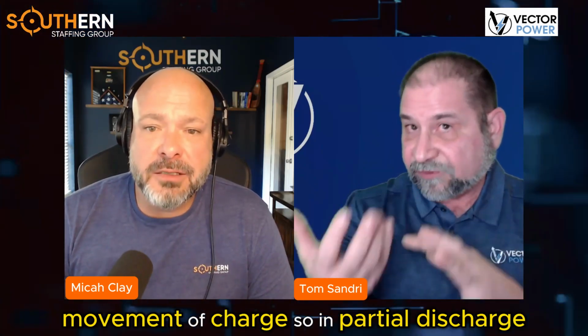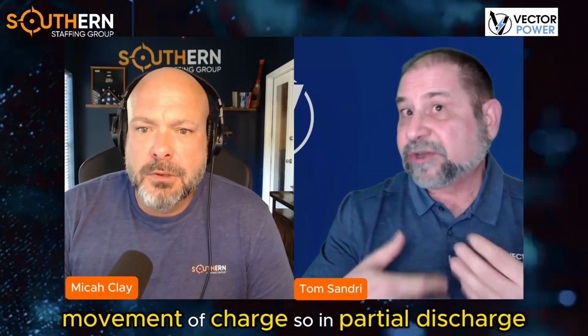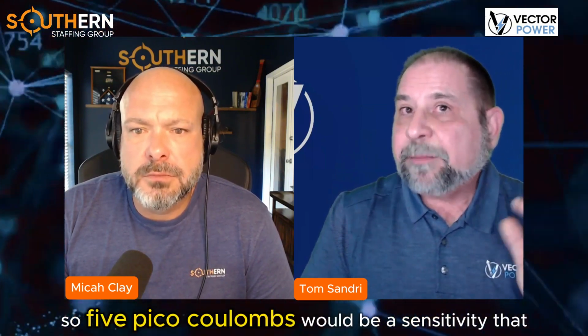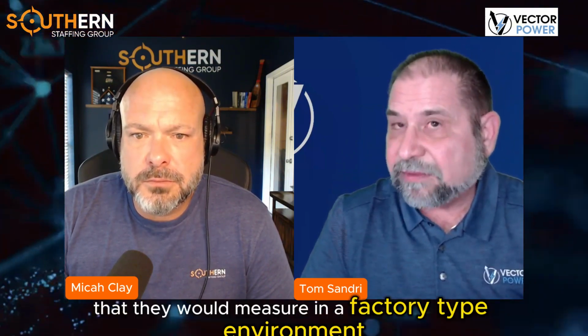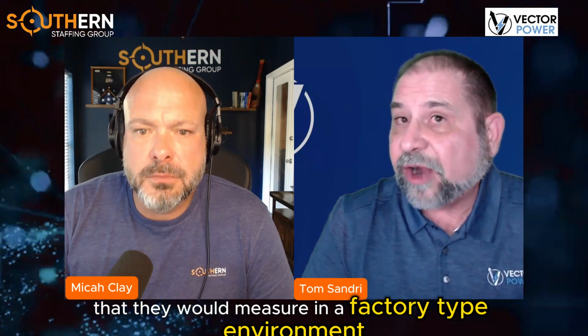The factory measurement sensitivity level is what they call 5 picocoulombs. A coulomb is a measurement of charge, movement of charge. So in partial discharge, we talk about the movement of charge. So 5 picocoulombs would be a sensitivity that they would measure in a factory type environment.